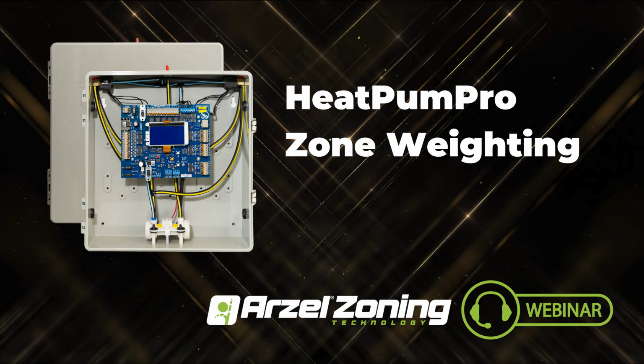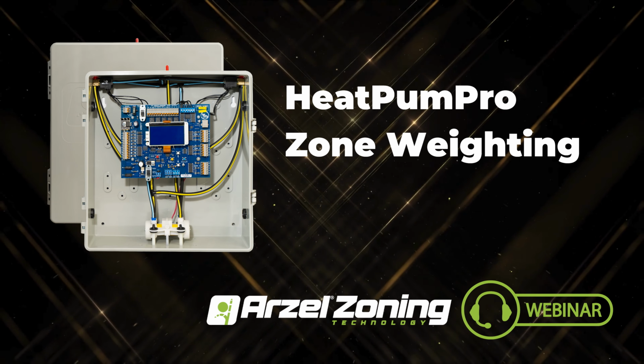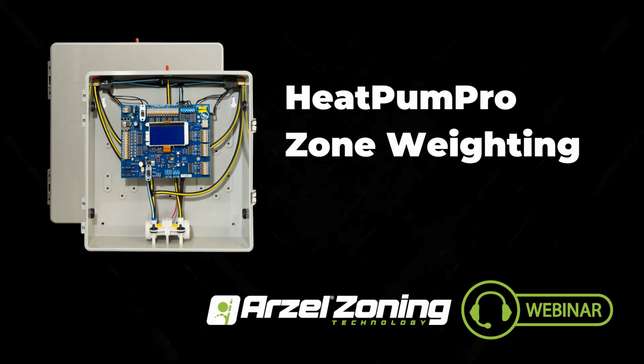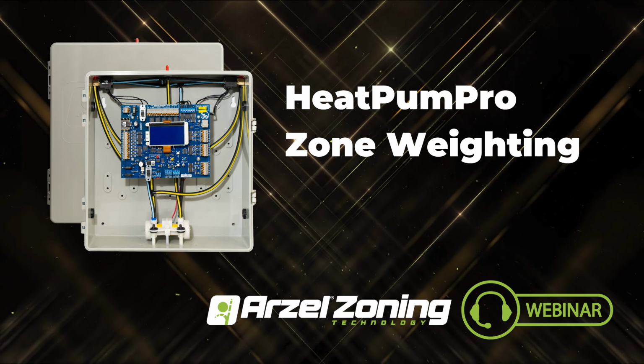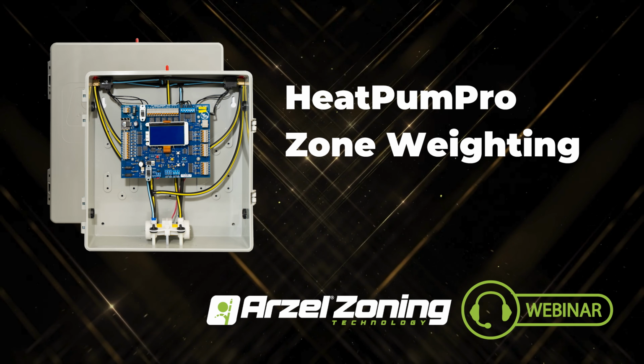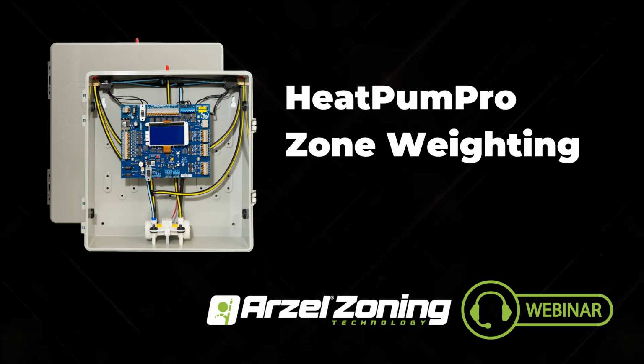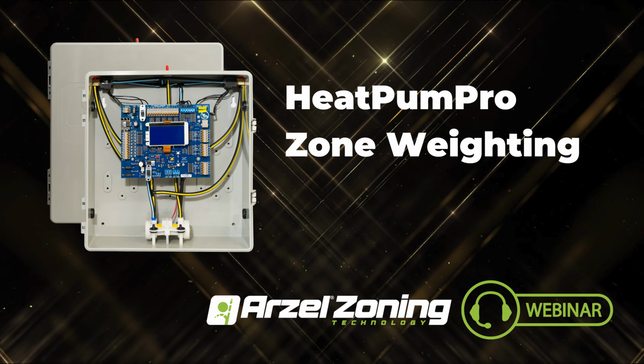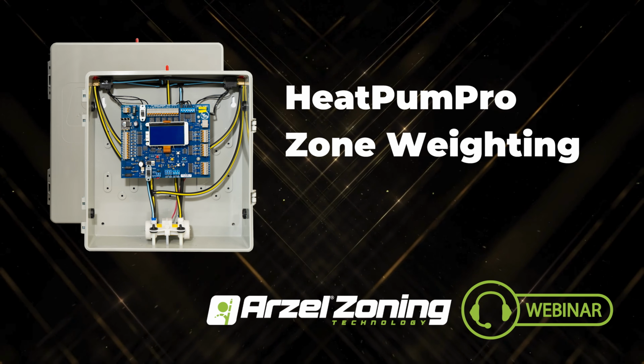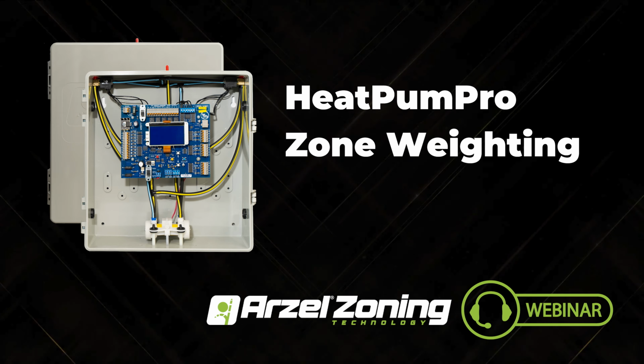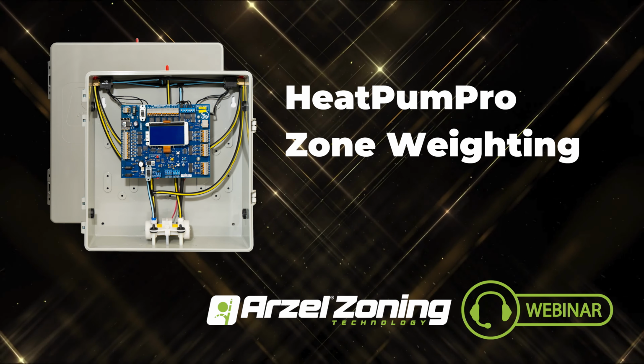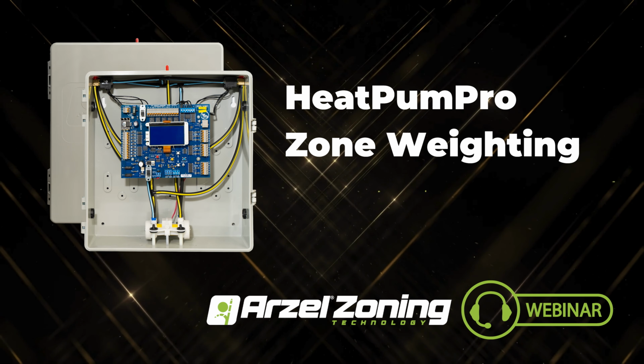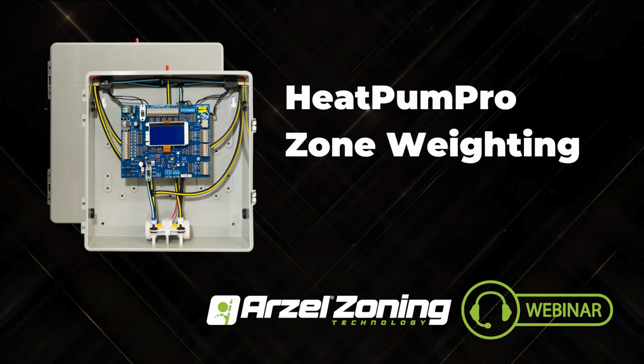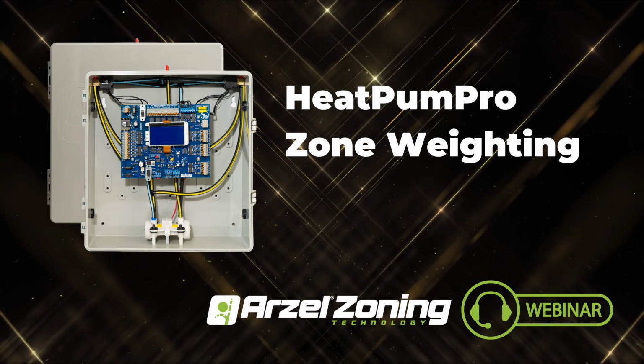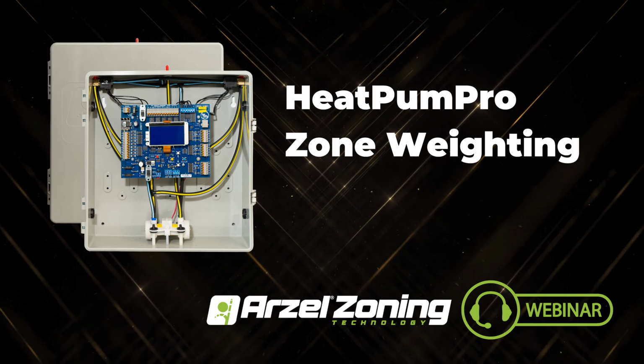So one of the things about the HeatPumPro is it's actually good for anything from a single stage conventional piece of equipment all the way up to a dual fuel application. The really nice thing about the HeatPumPro is you don't need any specific thermostat. It just needs to be heat-cool thermostats, and just single stage thermostats as well. This panel will control all of the staging internally, and this is how we actually operate and control your Y2 output and your W2 output on the panel.